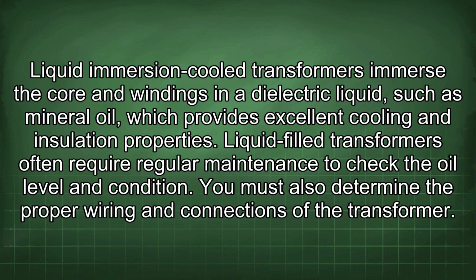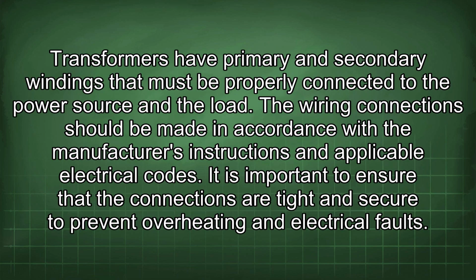You must also determine the proper wiring and connections of the transformer. Transformers have primary and secondary windings that must be properly connected to the power source and the load. The wiring connections should be made in accordance with the manufacturer's instructions and applicable electrical codes. It is important to ensure that the connections are tight and secure to prevent overheating and electrical faults.